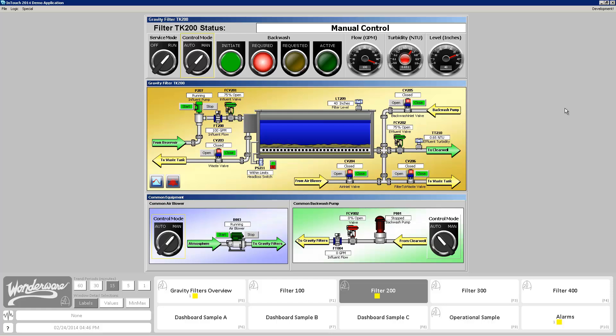I'm going to start with the graphic on screen right now, which is a demo I built myself many years ago. I'm going to point out many of its flaws because at the time I just didn't know any better. One of the flaws on this particular screen is inconsistent color coding. You're seeing that closed is indicated by red, stopped is indicated by red, there's a backwash required indicator in red, and a high effluent turbidity alarm also showing in red.